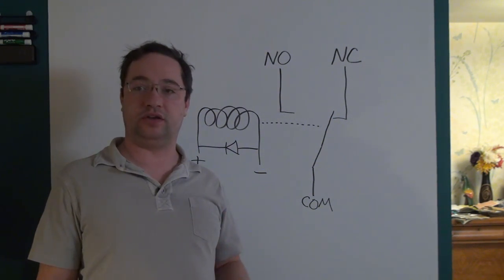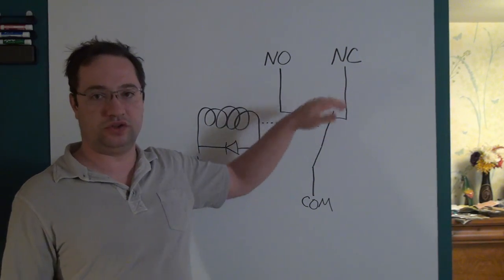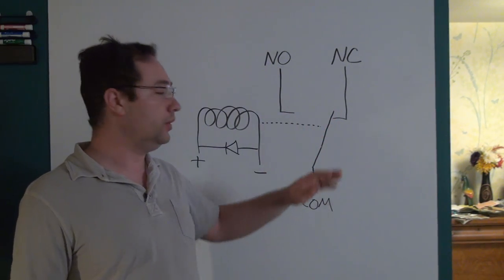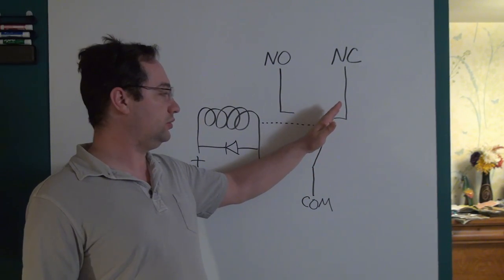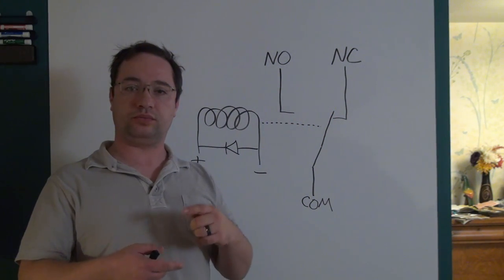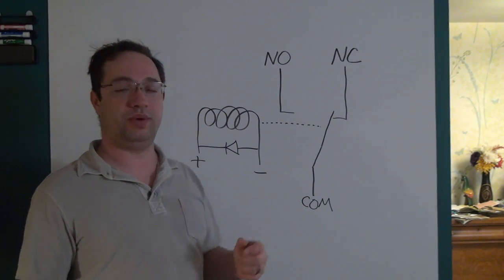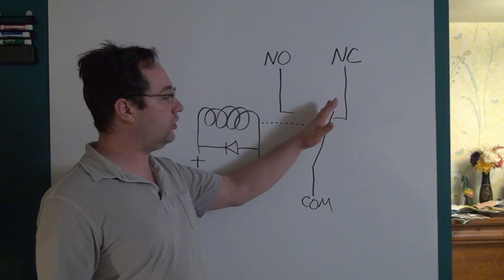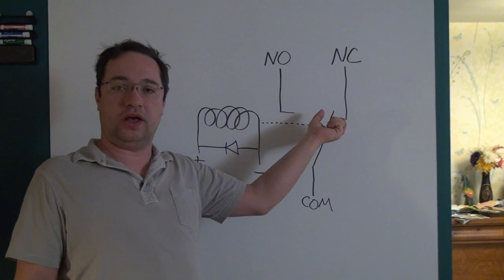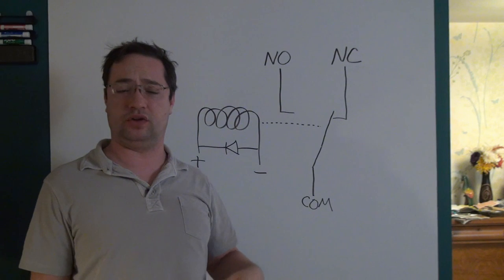For an inductive load like a motor, if your contact is normally closed and your motor is on and you energize the relay to shut off the motor, the inductive properties of the motor want to keep the current flowing. So as the arm starts to move away, you draw an arc, and that arc will last longer than that of a resistive load — which is generally bad.